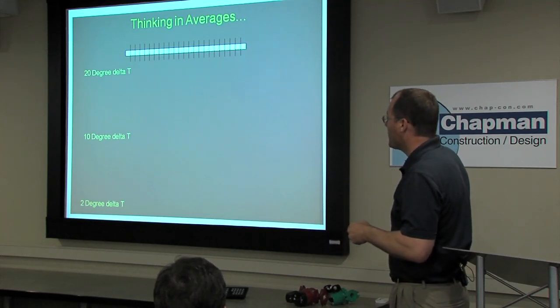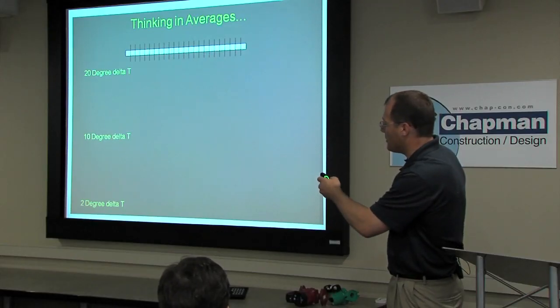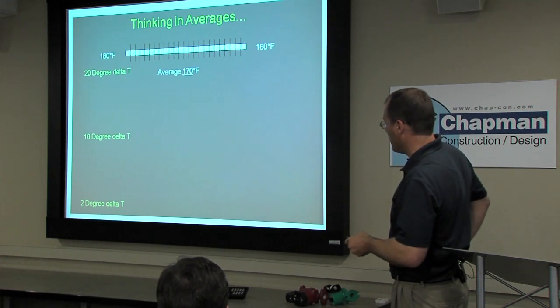One thing to think about for people designing systems is, you always talk about a 20-degree delta T. Why? That's always been kind of the industry standard for designing a hydronic heating system. But if we can slow down the water and still provide the heat, why not do that? We can talk about larger delta Ts, but you have to remember to think about an average water temperature. If we had a 20-degree delta T, we start out at 180, we come back at 160, our average is 170 degrees. So we should be sizing our heat emitter at 170 degrees.